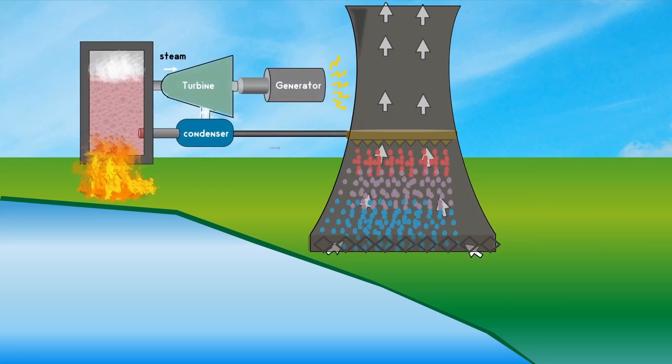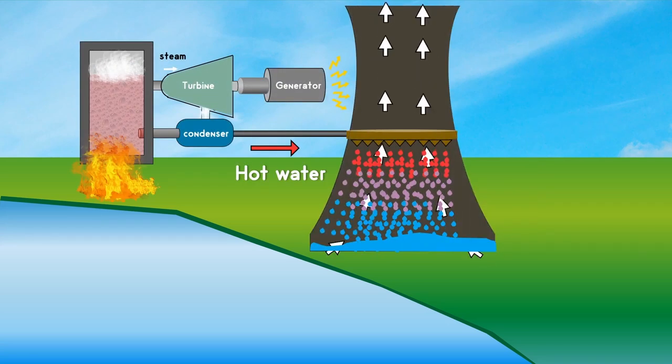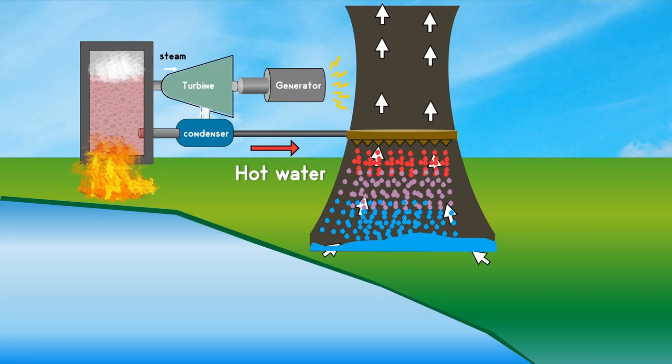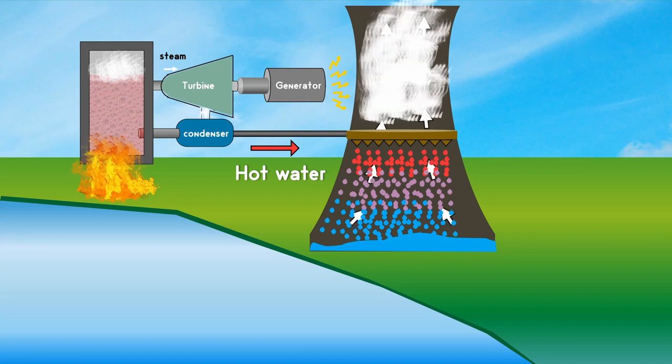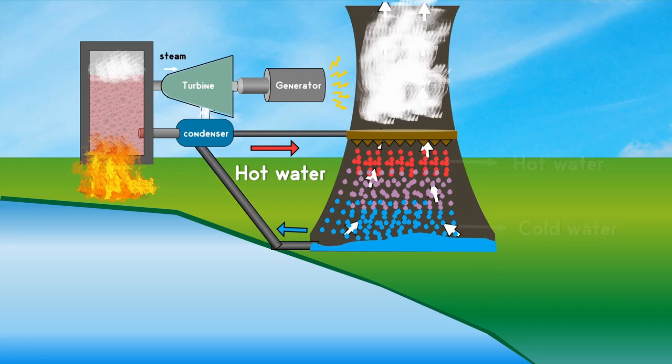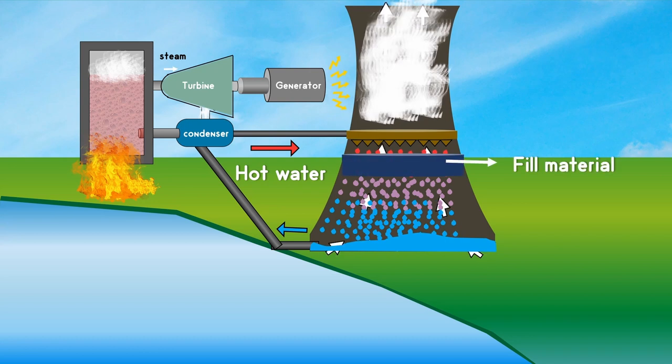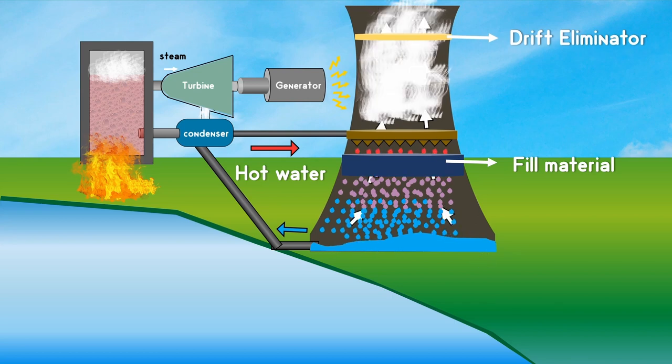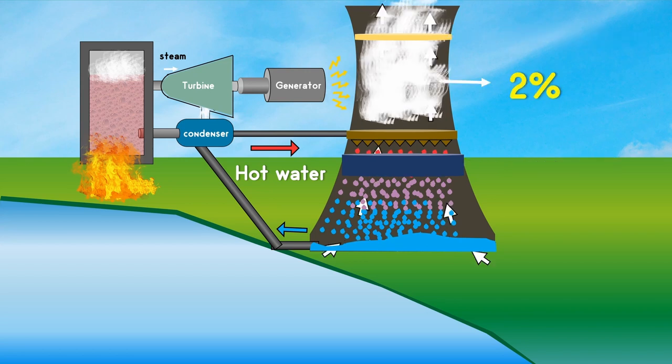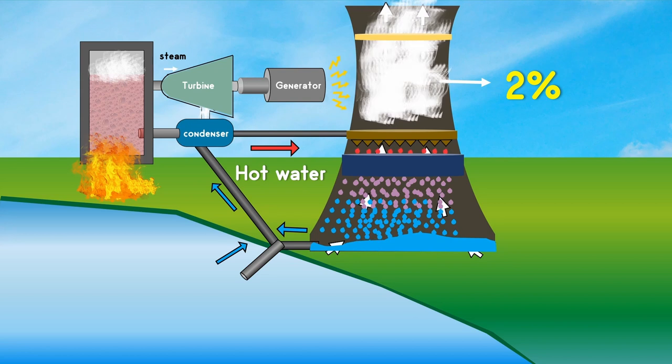The hot water is sprayed from nozzles within the tower. As the air passes through the water the heat is exchanged and some of the water evaporates. The cold water is collected at the bottom which can be reused. A key component of cooling towers is the fill material which further helps to maximize air water contact. The drift eliminator is also present which prevents the escape of water droplets. During this process around 2% of water is evaporated. So the makeup water is added to compensate the water losses in the circuit.